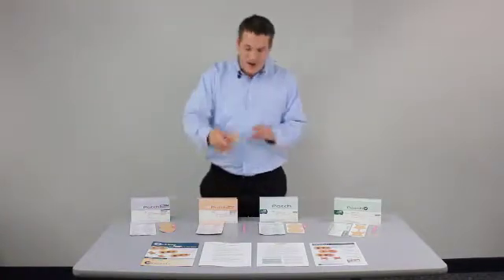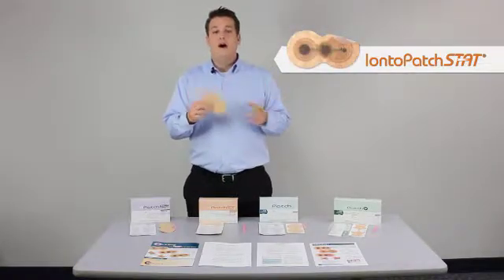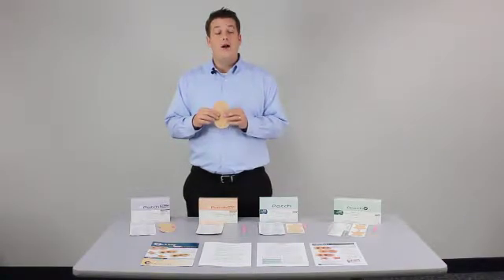The next product is our IontoPatch STAT. This is an 80 milliamp minute patch where you get the drug delivered in four hours, so it's really designed for those patients that require a shorter wear time.